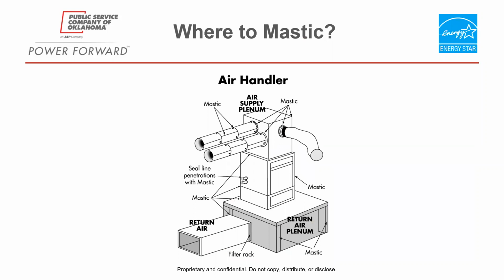Getting to mastic and air sealing. Basically, when you're looking at an HVAC system, including all of the ductwork, any two pieces of material that come together, or any seam along that material, should have mastic on it. It's a putty-based material that goes over those seams and seals everything up.